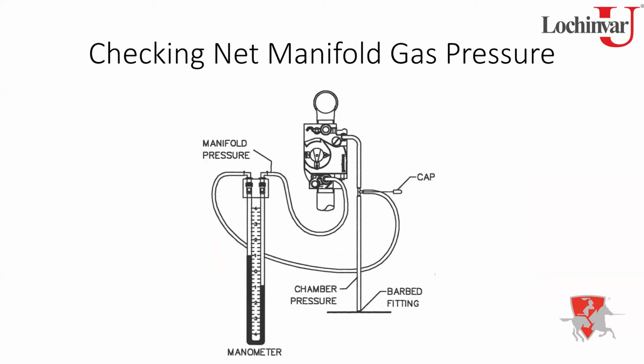Now, typically the way I set these up in the field, I'm going to set that deck pressure first. I'm going to adjust my air shutter to give me the deck pressure that I'm looking for: 1.4 to 1.6, somewhere in that range. I think the manual says 1.8, and I think that's a little on the high side. So 1.4 on the low end, about 1.6, gives us a nice happy medium. Once I've got that air set to where I want it, as far as that deck or chamber pressure is concerned, then I can look at that manifold pressure.